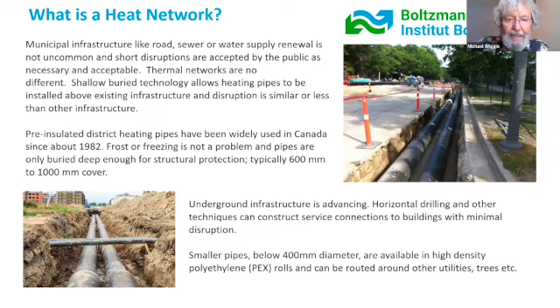The University of Ottawa has a combination of steam and hot water, one of the more modern systems around on the hot water side. Ottawa has just totally refurbished the whole district energy system serving government buildings, and they're looking at expanding to serve the rest of the community as a possibility. You get shallow buried insulated pipes now, not like the old days where you put steam pipes in tunnels. You have pre-insulated pipes with high-value polyurethane insulation and a polyethylene jacket. You only need to bury them about 600 millimeters underground for structural protection, and then you can start linking things together.